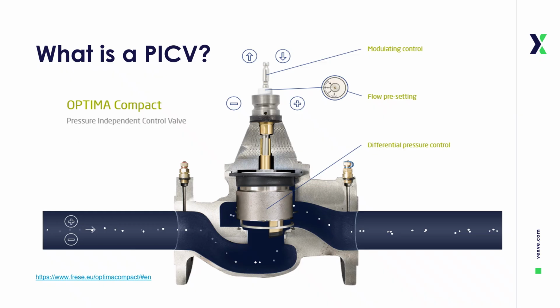Furthermore, unlike all other PICVs in the market, the Optima Compact is designed in a way so that the motion of the actuated piston is unaffected by the presetting of the valve opening, since the direction of the piston is vertical while the presetting is set in a horizontal movement by means of two separate parts. For more details on the Optima Compact PICV, you can explore further at Frese's website.